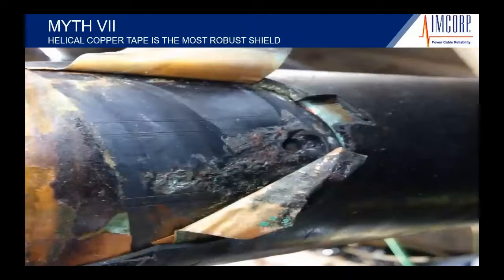Another myth is that the copper tape shield is a robust shield. So I use this for the industrial application that we see today. This is a common design. The copper tape shield overlapping is only used in the industrial market today, as a fairly common practice. The renewable market and the utility market use a concentric neutral. Now, when this is a new cable, the shield is a good shield. It's very robust. There's really no issue. Typically, when we find problems with cables or termination, it's usually at the termination itself.